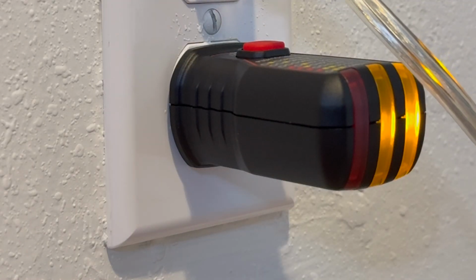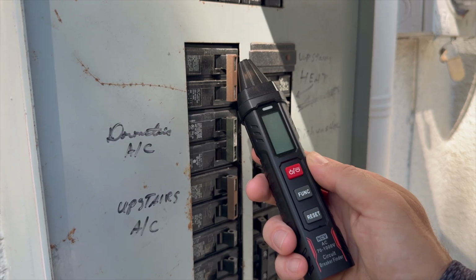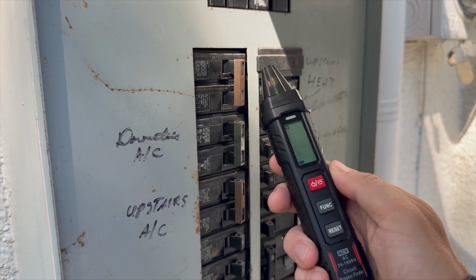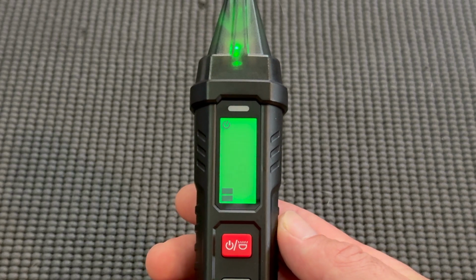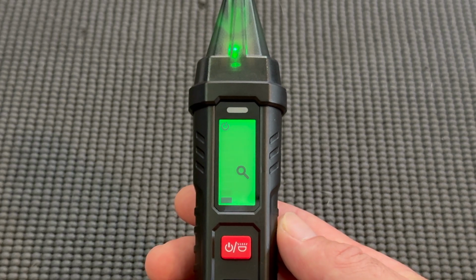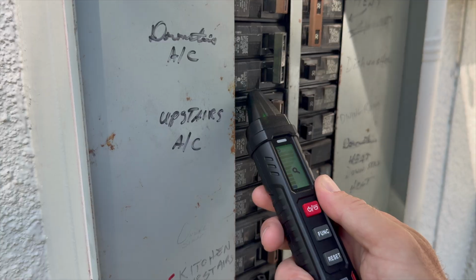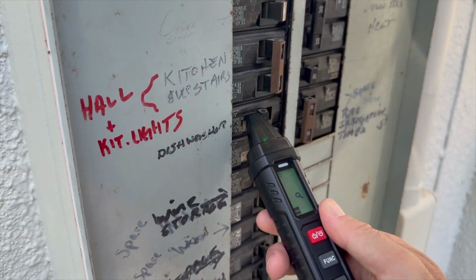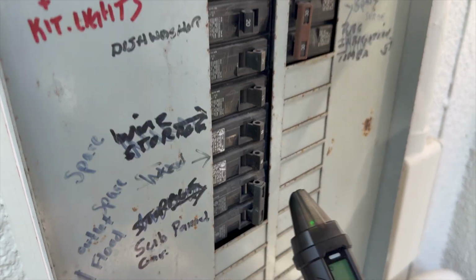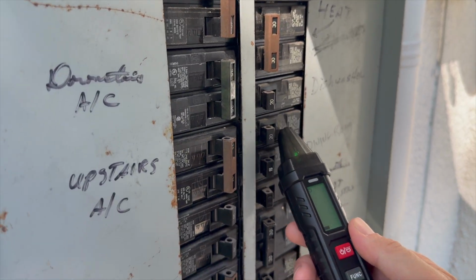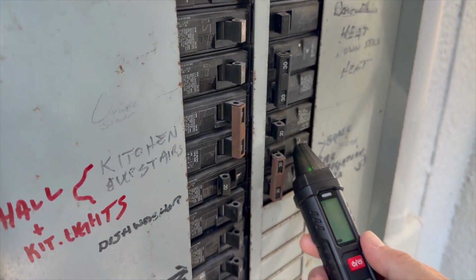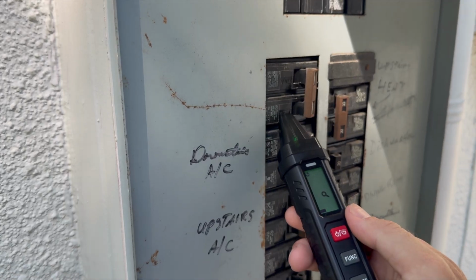To find the correct breaker to an outlet, plug the transmitter into the outlet you want to identify, then turn on the receiver. It defaults to circuit breaker finding, and you'll know it because you'll see the bars stacking up. Now head over to your electric panel. You'll make 2 slow passes moving in the same consistent direction. The first is for the receiver to learn your panel, and the second one will identify the correct breaker by making an audible beep.